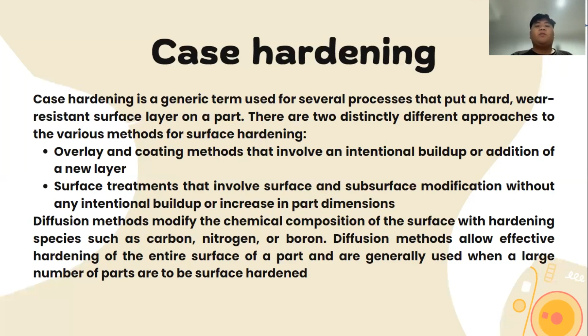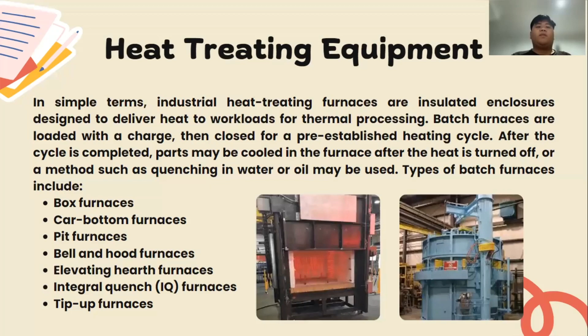Heat treating equipment. In simple terms, industrial heat treating furnaces are insulated enclosures designed to deliver heat to workloads for thermal processing. Batch furnaces are loaded with a charge for a pre-established heating cycle. After the cycle is complete, parts may be cooled in the furnace after the heat is turned off, or methods such as quenching in water or oil may be used. Types of batch furnace include box furnace, car bottom furnace, pit furnace, bell and hood furnace, elevating hearth furnace, integral quench or IQ furnace, and tip up furnace.